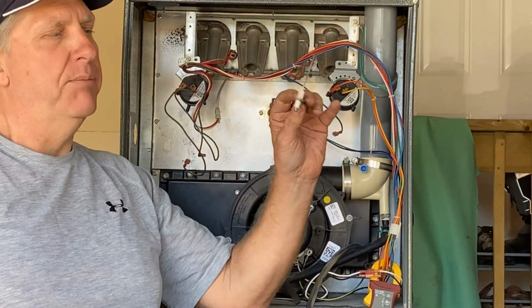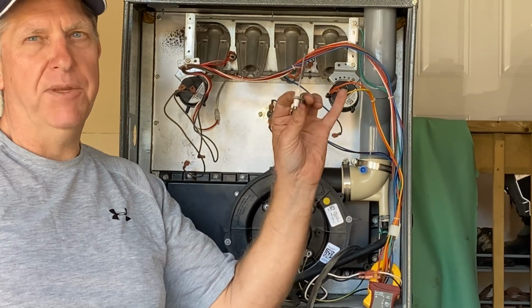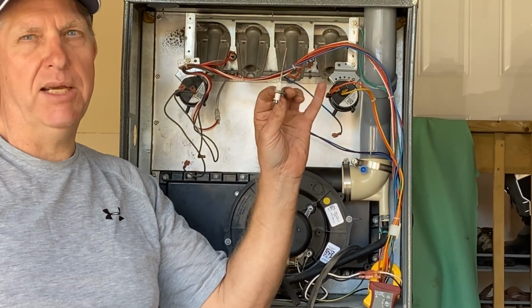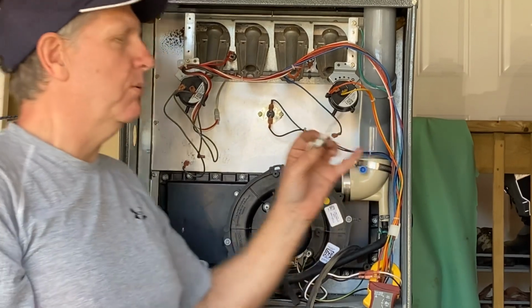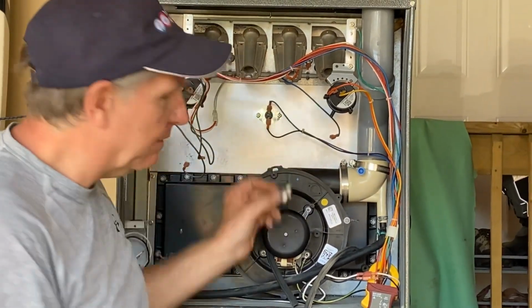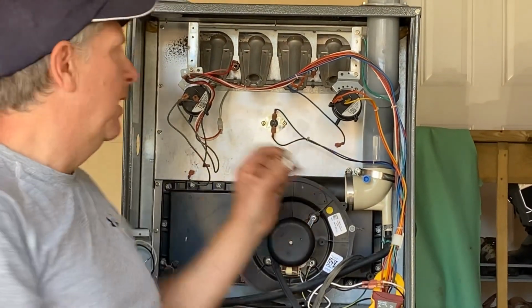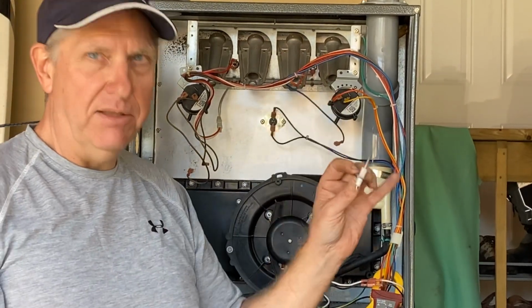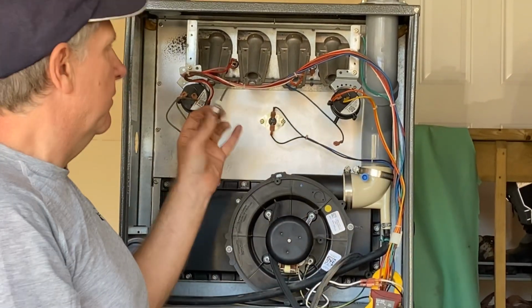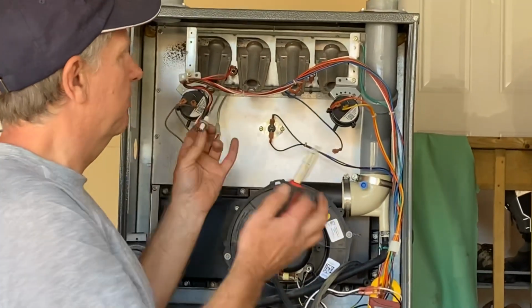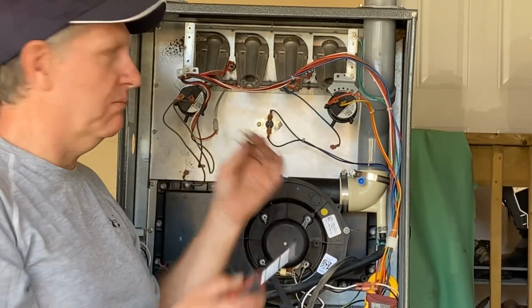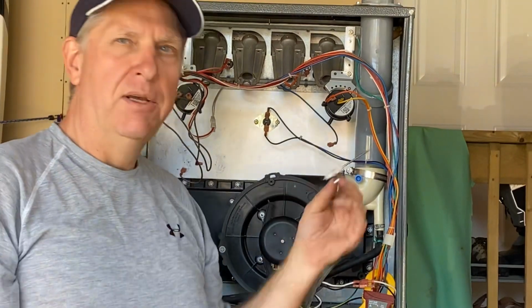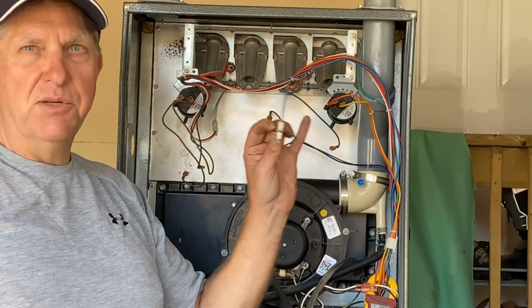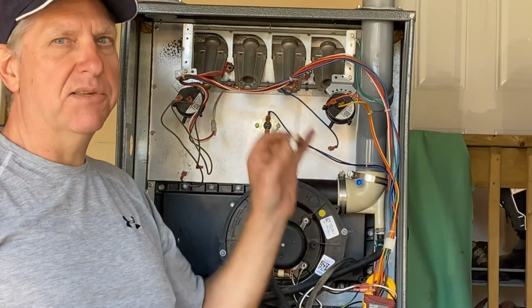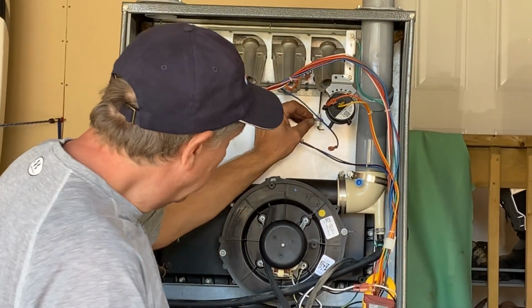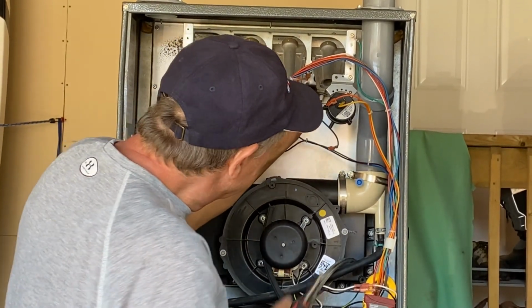You can test these with your meter. It's a millivolt reading that you're looking for. There's a certain way to do it, but it's important that the flame sensor is working properly. If there's a flame and this doesn't sense it, your furnace won't work. If there's no flame, if for some reason the igniter happens but the burners are plugged or whatever, this will sense that there is no flame and shut the furnace down. It's a safety control, so that's what its job is.